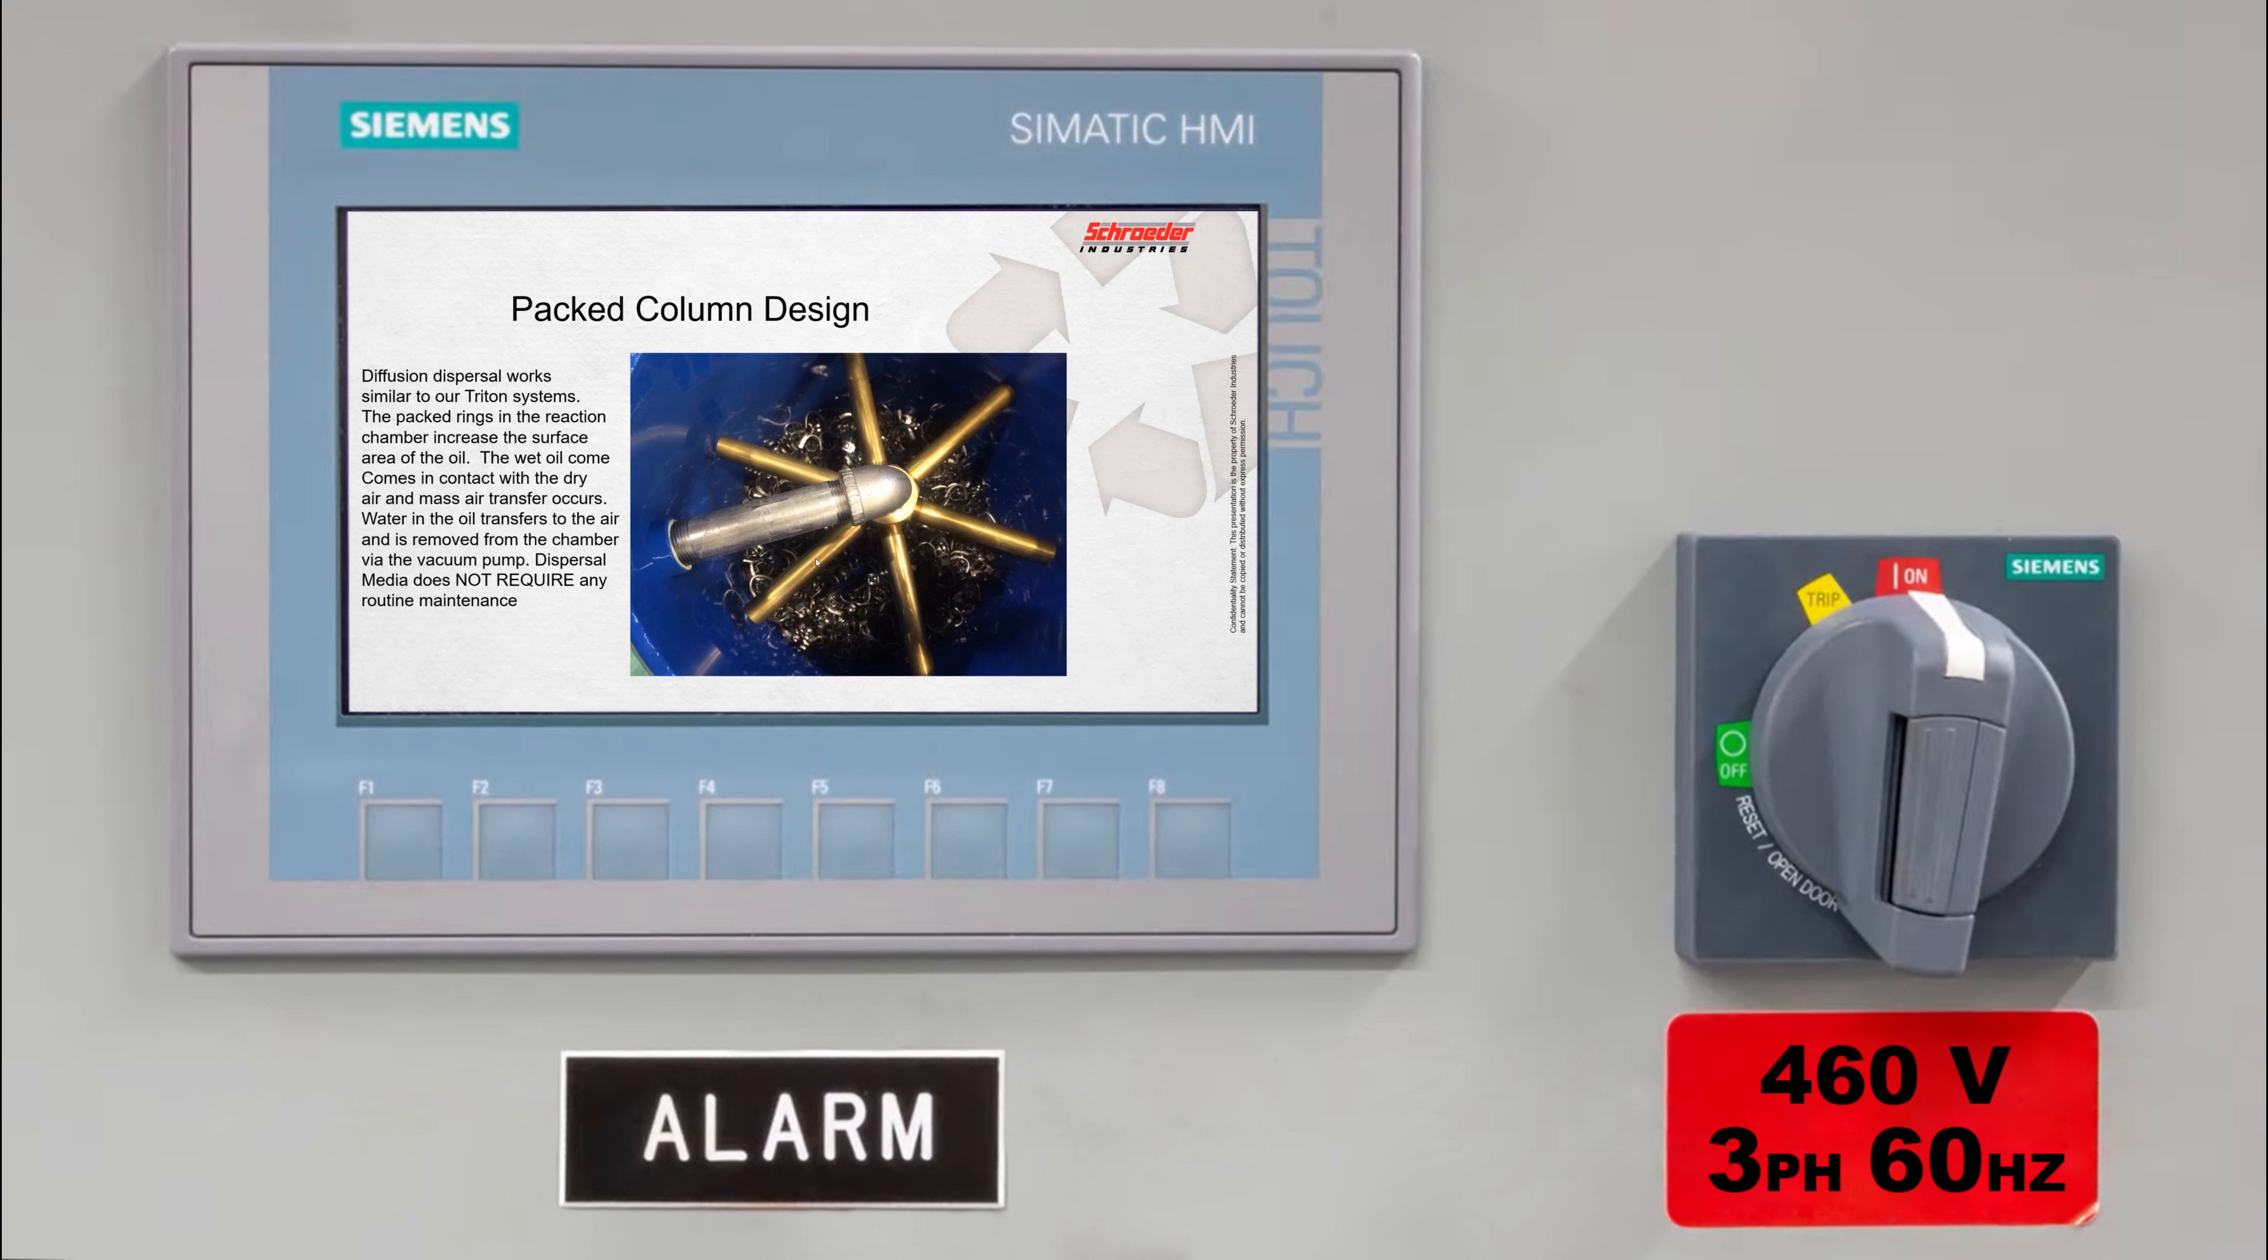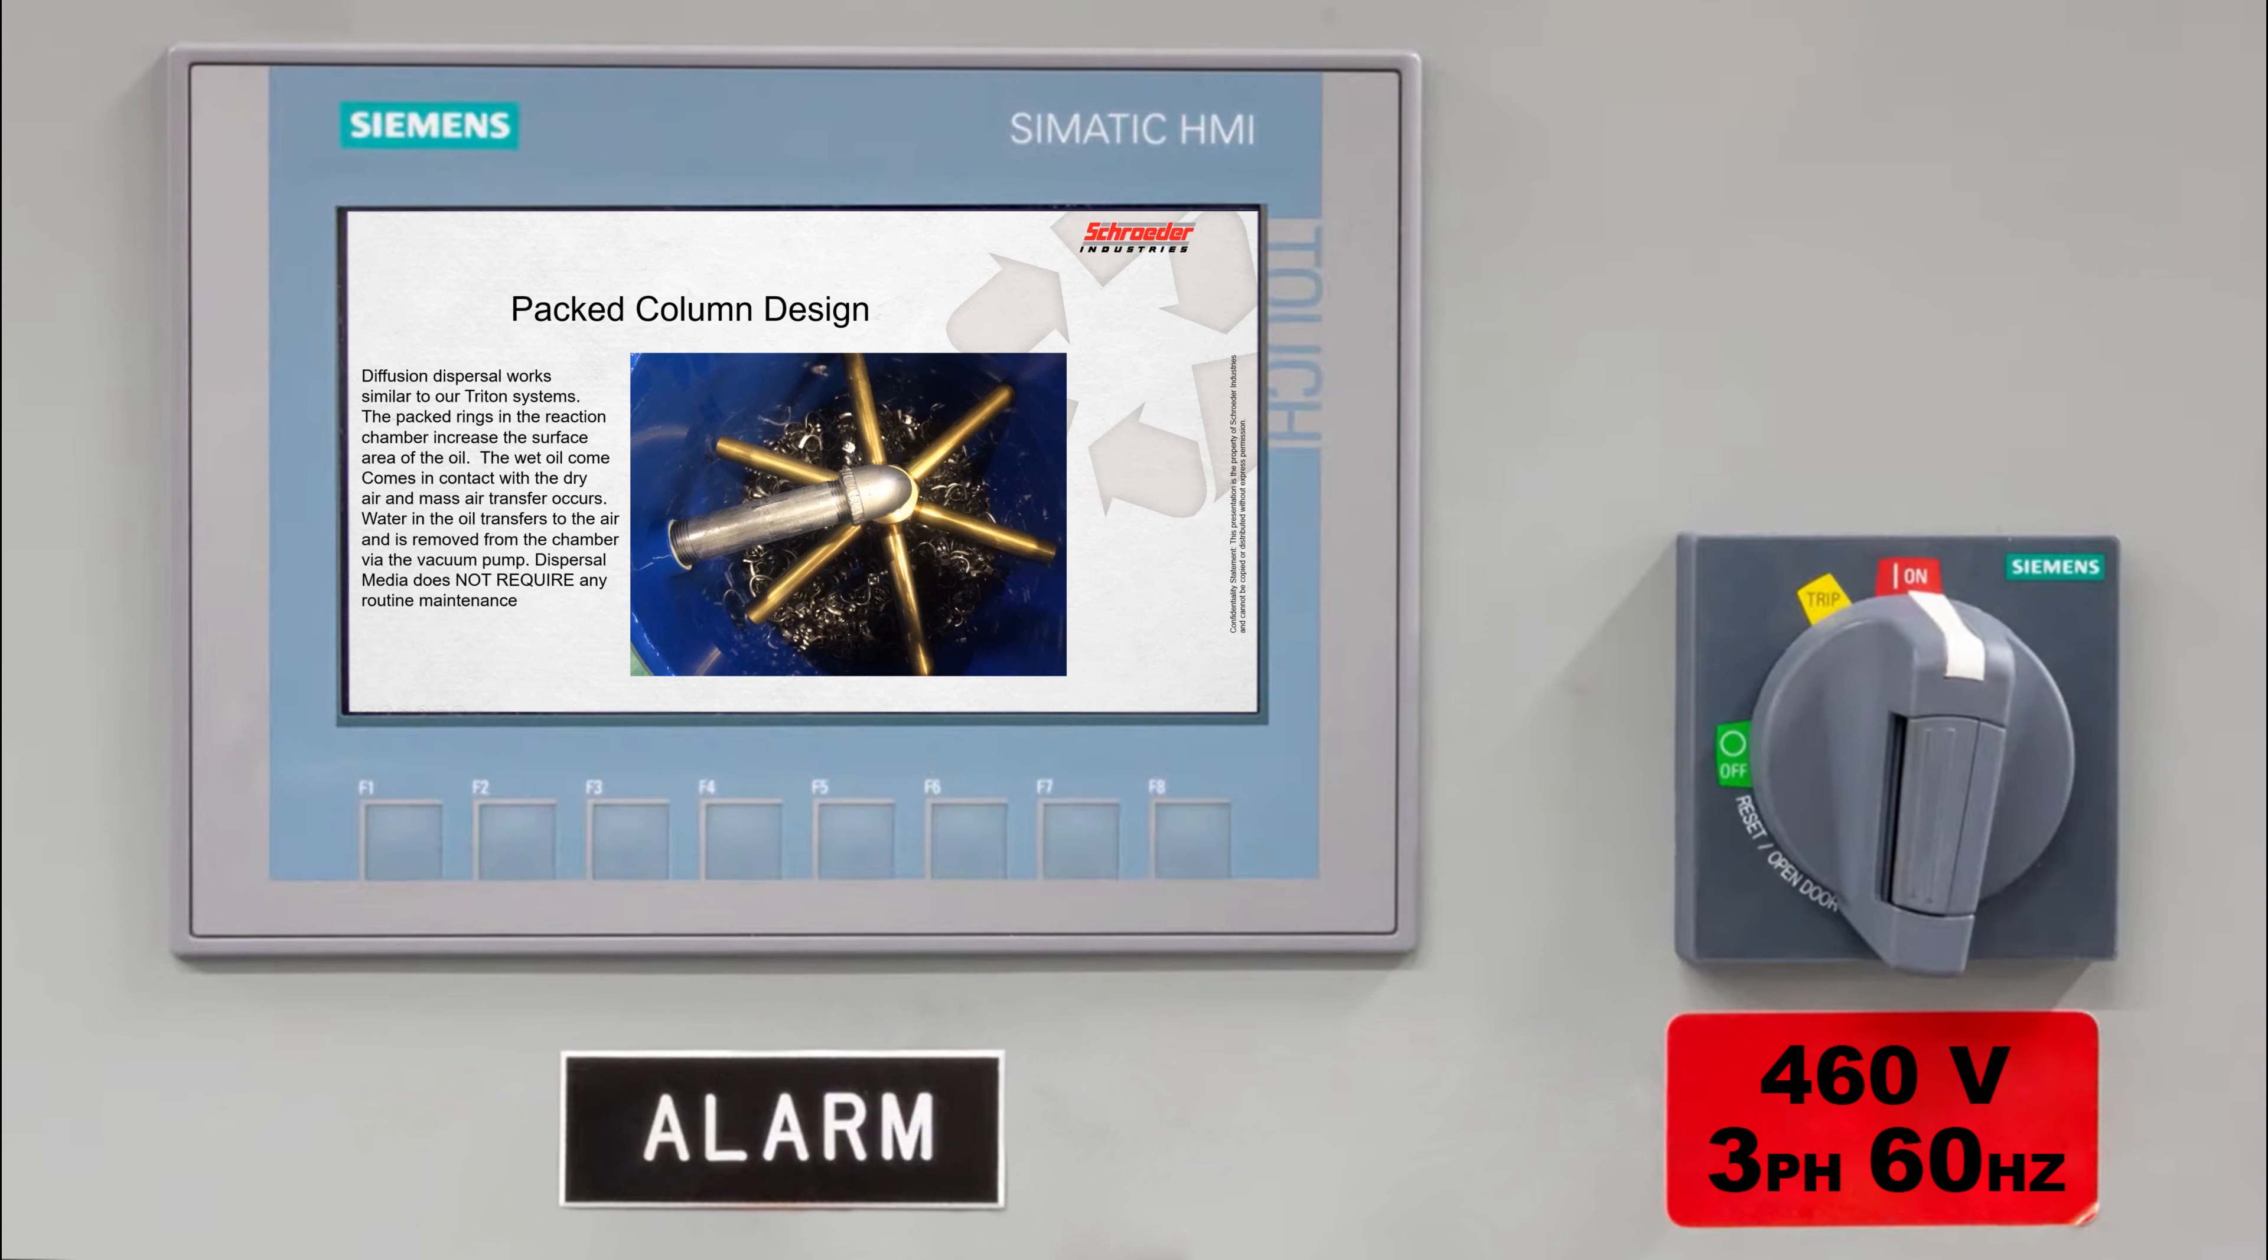Now a lot of strengths come up with the mass transfer diffusion method. We're going to remove free dissolved water gases, get it much below the saturation point. We can also drop it into single digits. A viscosity range up to 700 centistokes, very low maintenance on it. The vacuum pump only requires an annual oil change based upon about 7,000 hours, and then you have your intake breather and your particulate elements, but that's really your maintenance that's used on this. It's very efficient at a lower heat, low vacuum, has a high uptime reliability, ease of use and performance.